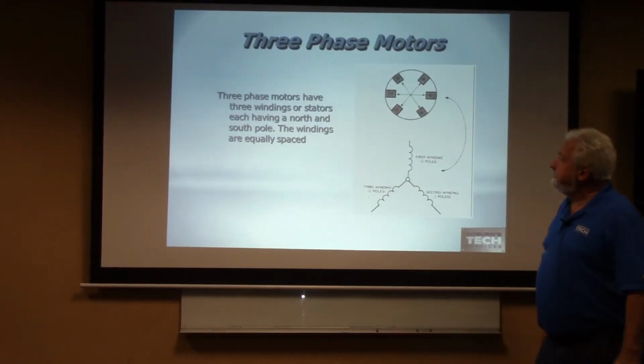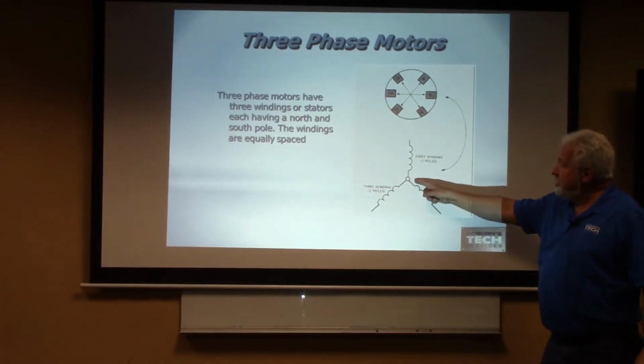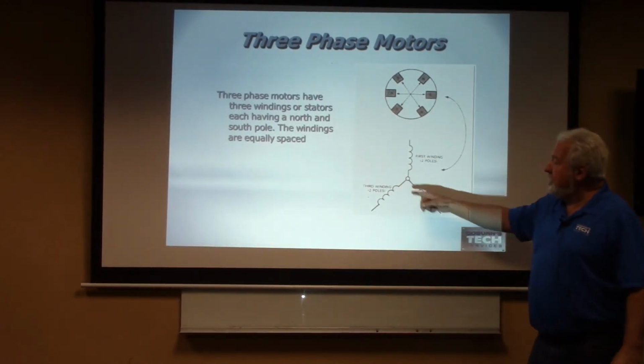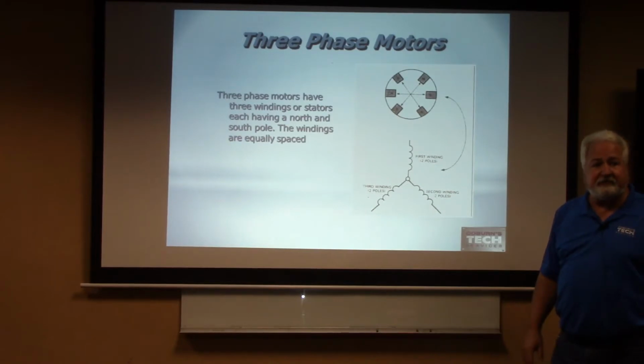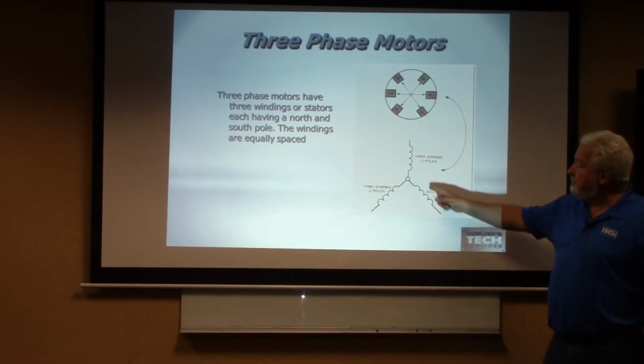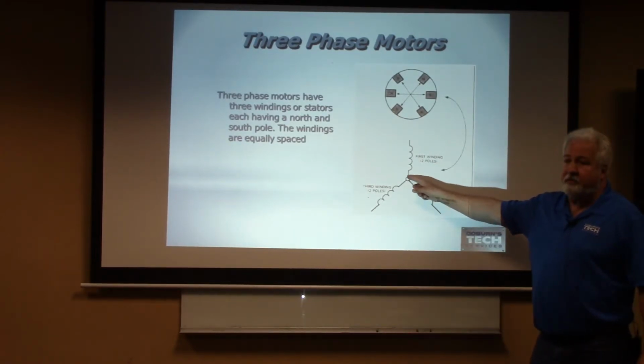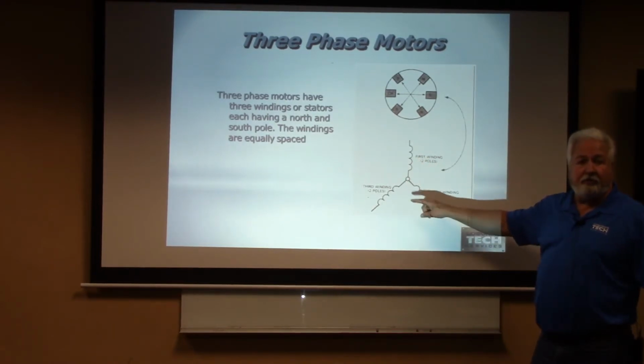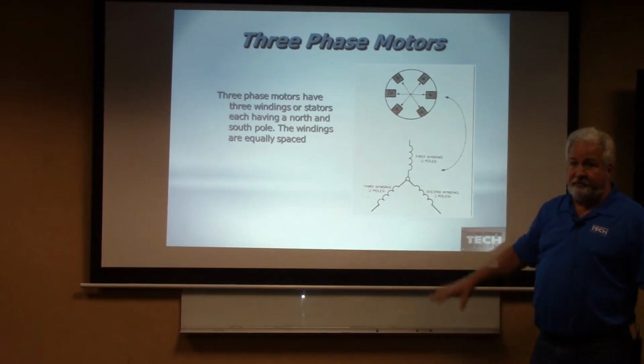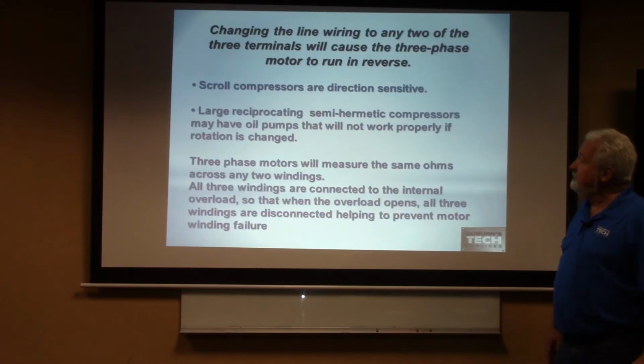Three-phase motors. You have 3 separate windings. All of them are going to have the same resistance. And typically you're going to have one overload right there in the middle. So if the one overload opens, all 3 windings are going to be open. Does everybody get that? All right.